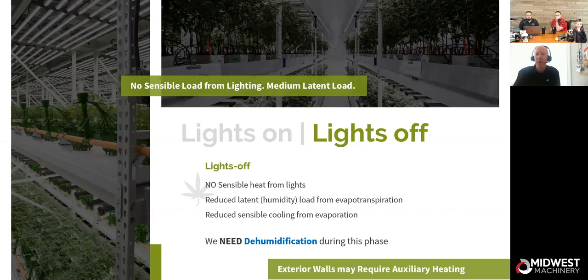The other side of that coin is if you were relying on your air conditioner to remove moisture during lights off, why would the air conditioner even run without the lighting load? It won't. Unless there's some sort of heat gain coming from the external walls or somewhere else in the room, we don't need to be adding much cooling, if at all any, during the lights off period. So our primary load with lights off is going to be a dehumidification load, and only a dehumidification load.